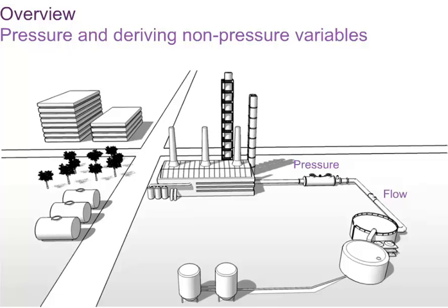These are flow rate in a pipe, level of fluid in a tank, density of fluid or interface level of two fluids in a tank. For density of fluid and interface level, a differential pressure transmitter is always necessary, very often combined with diaphragm seals.